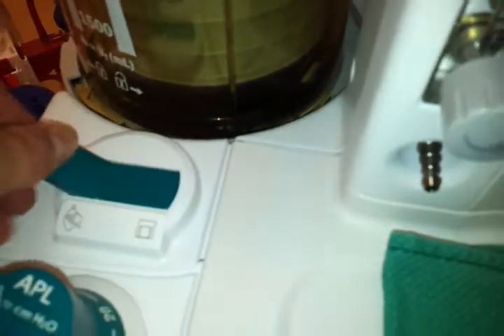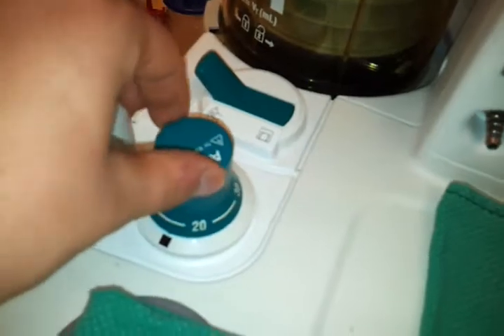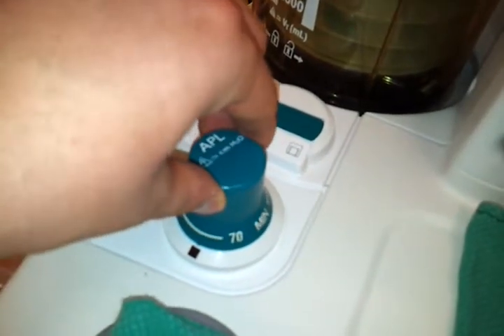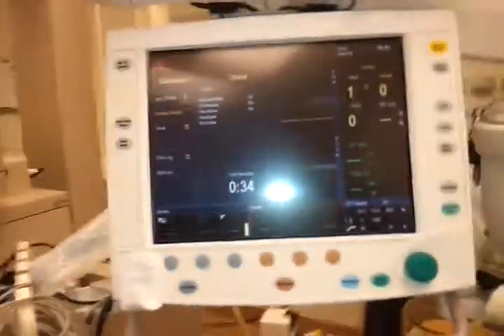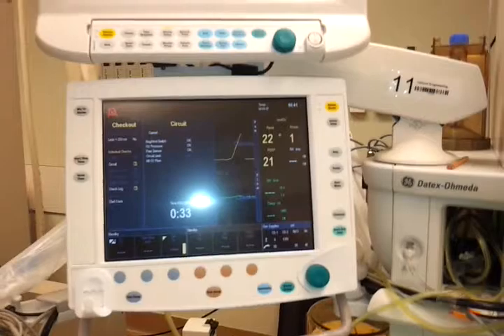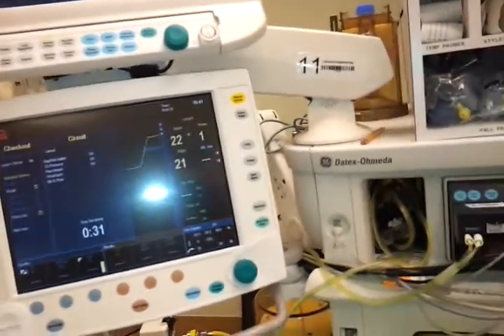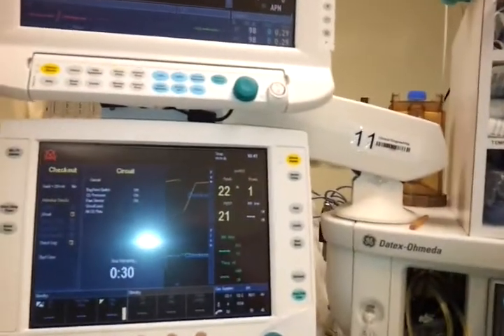Okay, so you want to occlude the patient Y, which is still occluded down there. So you want it switched to bag, and set the ACGO switch to circle, which it's still set at circle, so point it up. Yeah. And then you want your APL valve between 30 and 70. You should hear the little click when it goes above 30. Yeah. So, and that's all you need for this one. So, 34 seconds. Yeah, I guess we'll just wait for this one to finish.